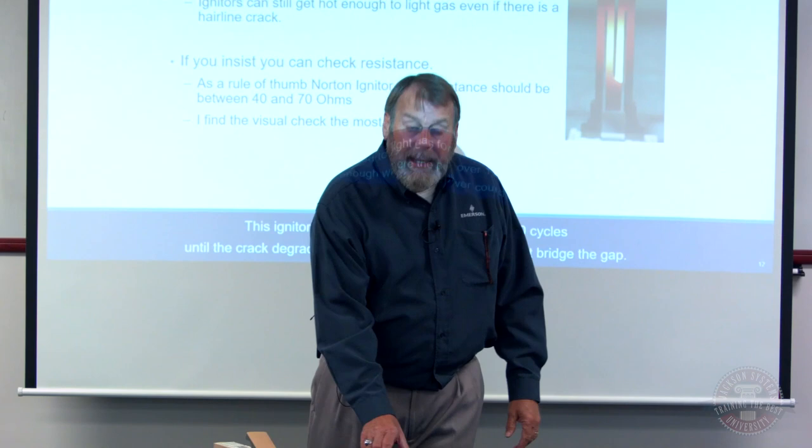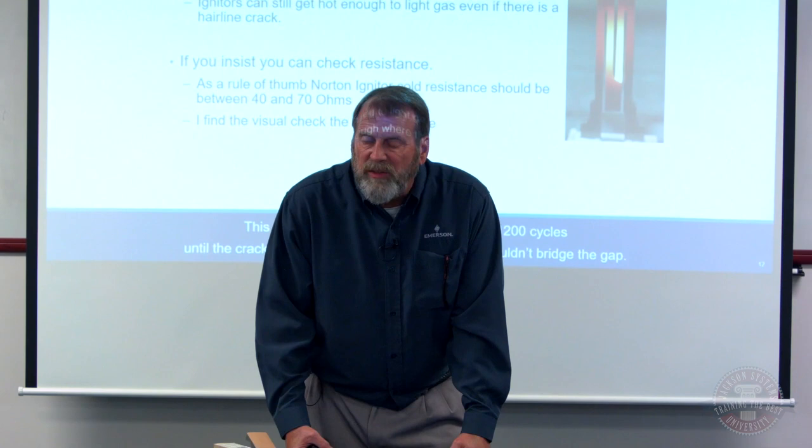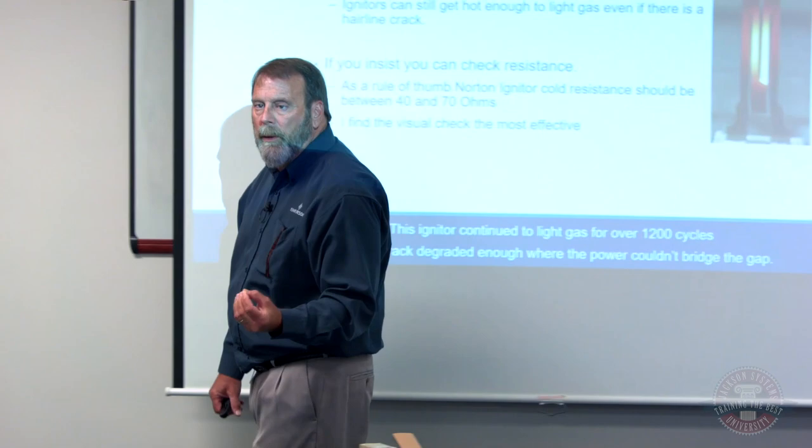Anybody want to guess how many cycles I got out of that puppy? Over 1,200 cycles before it finally got big enough where it broke. In St. Louis, that's almost a full heating season. So the point I'm making in the 15-second spot check, watch the igniter from the time you turn it on to the time it ignites and look for the hot spot.